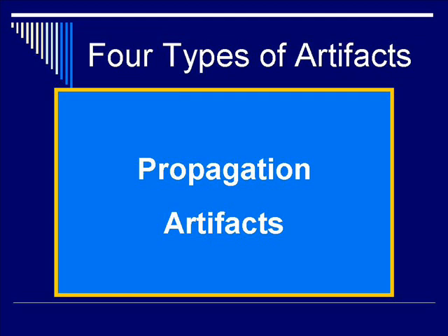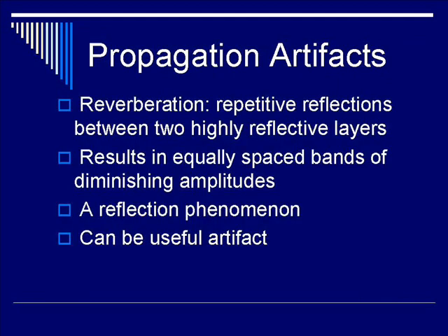The first artifact under propagation that we want to discuss is reverberation. Reverberation is an intuitive phenomenon that you associate with sound, with light — any phenomenon that bounces back and forth around a central object. In this case, we have repetitive reflections of ultrasound waves that occur between two or more highly reflective layers. The result is equally spaced bands of hyperechoic signal that become diminishingly less in amplitude distal from the object of interest. In short, it is a reflection phenomenon, but nonetheless a very useful artifact.